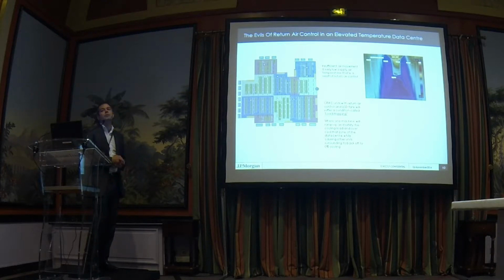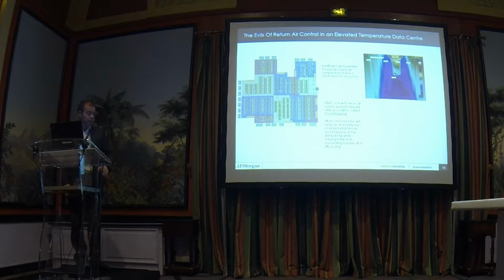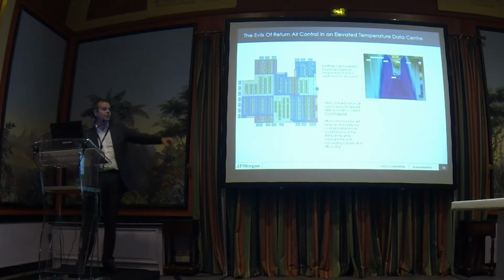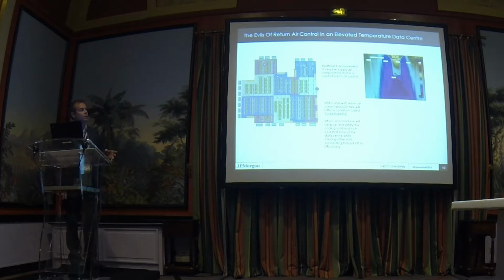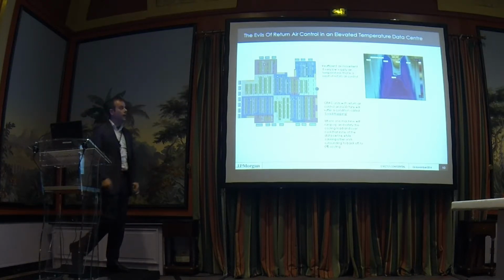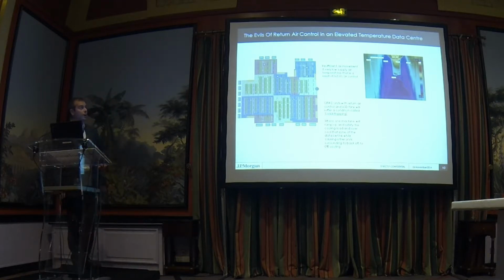You never run your data center with all your floor tiles open. If you walk through your data center floor through the cold aisle, and if anywhere along there you feel more air coming out of any one position more than the rest of it, you've got an unstable static pressure on the floor. What you need to do is go along in your data center with a screwdriver. Any floor tile that's absolutely blasting air, shut it back.